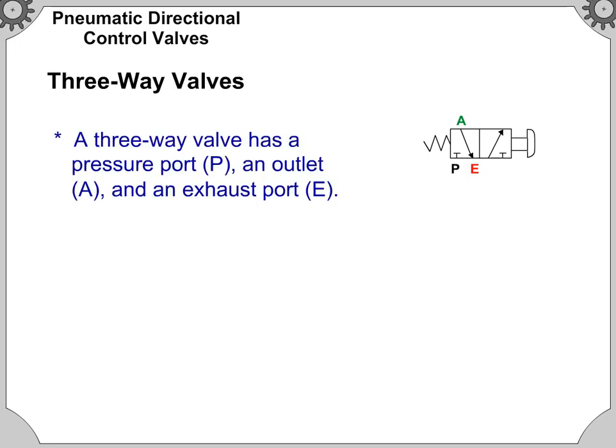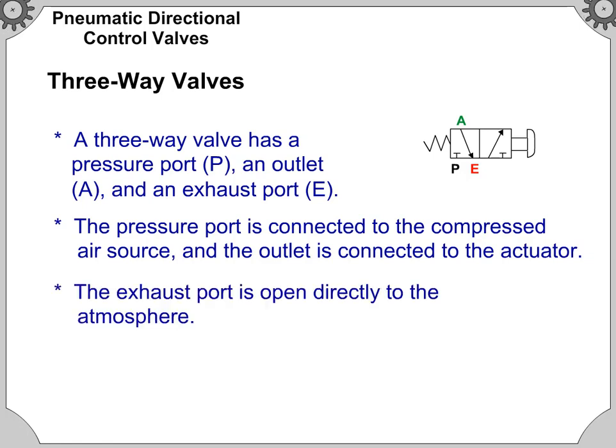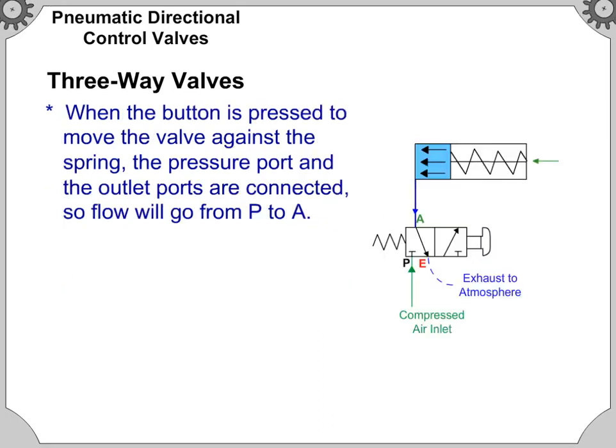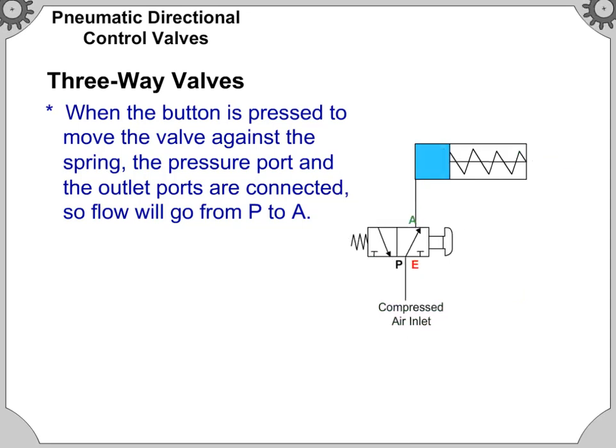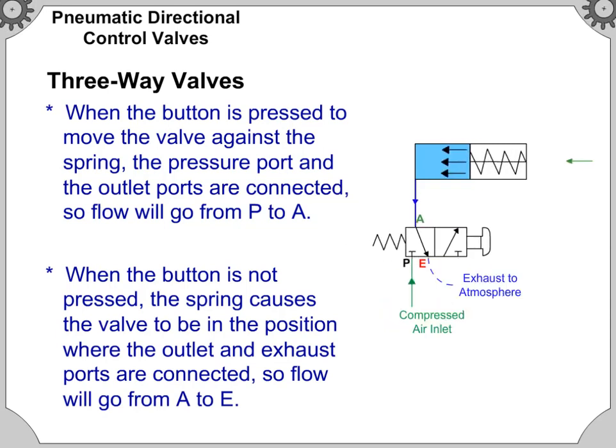A three-way valve has a pressure port P, an outlet A, and an exhaust port E. The pressure port is connected to the compressed air source and the outlet is connected to the actuator. The exhaust port is opened directly to the atmosphere. When the button is pressed to move the valve against the spring, the pressure port and outlet ports are connected so flow will go from P to A. When the button is not pressed, the spring causes the valve to be in the position where the outlet and exhaust ports are connected, so flow will go from A to E.